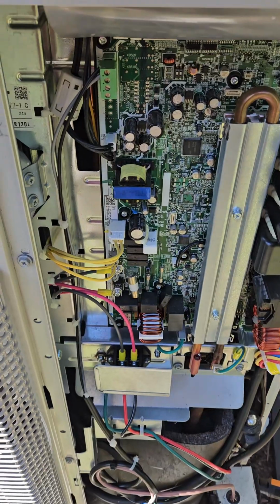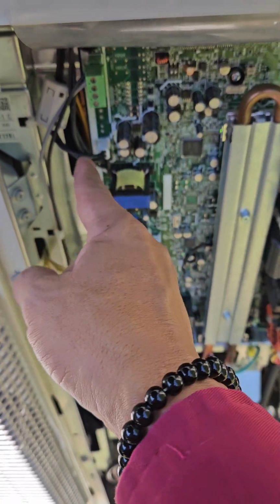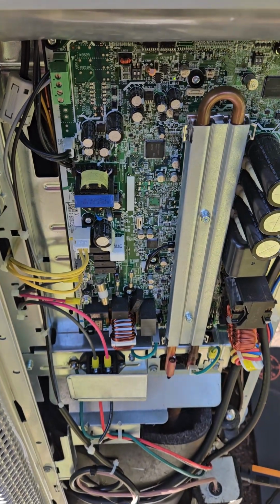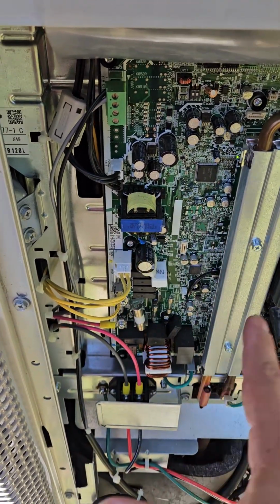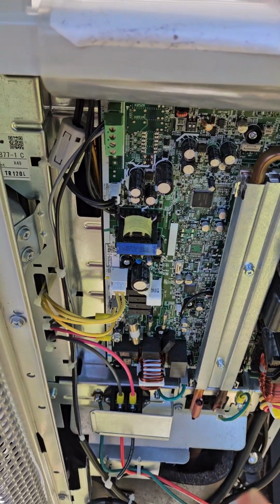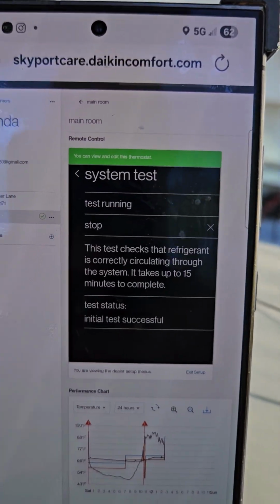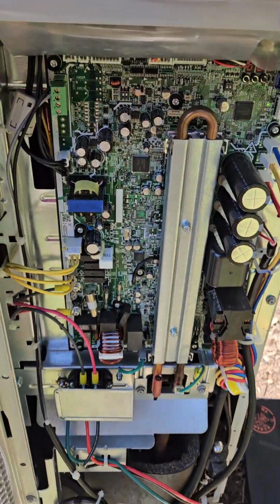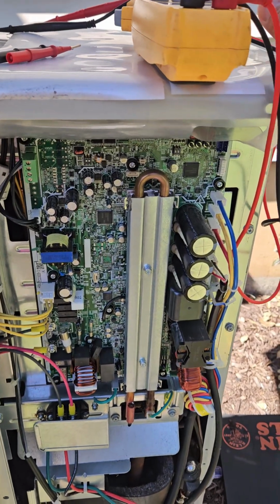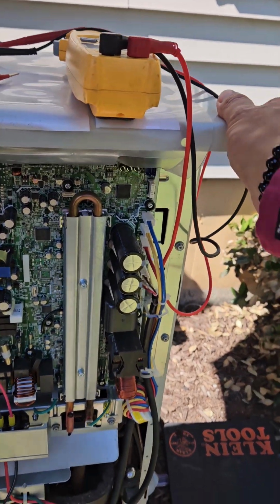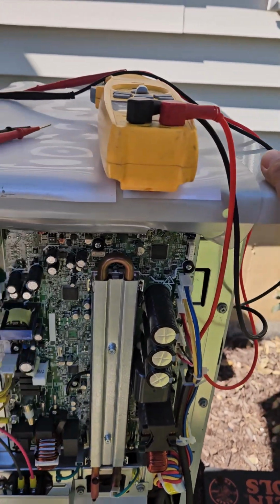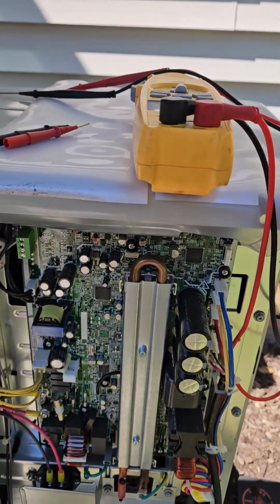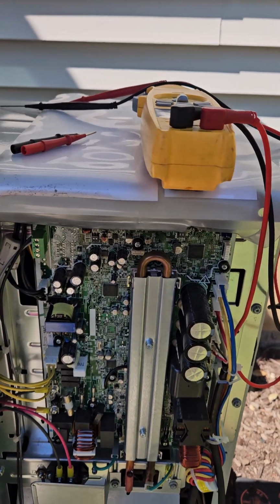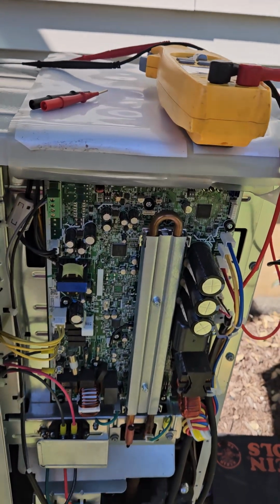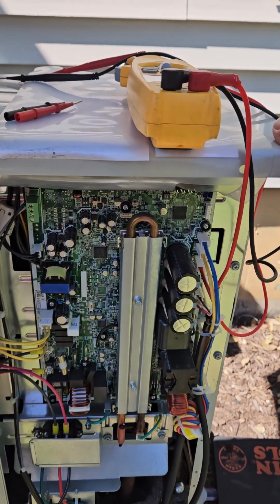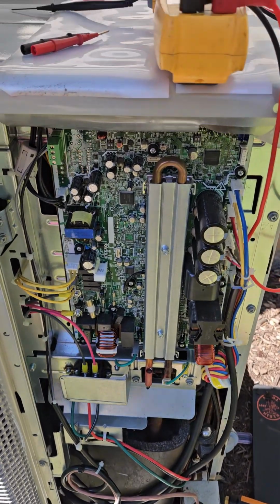Alright. Okay, so the pressure, resistance, and the actual voltage coming out into the actual switch, that's fine. So all the part of the board is sending the right inputs, and the switch is responding to that, so nothing is wrong with this. I just put the thermostat on running test, as you can see right there, so that way I can see if there are any issues with the code 13, because once the system runs in test mode, it'll tell me if there are any subcodes related to the code 13. So it could be 13 or 1 or 2 or 3, and I think it's all 4 as well. It depends on those codes. After the test, I can see exactly what's going on. So once I receive that subcode, if it is 1, I'll let you guys know what that code means and what we need to do in order to fix that problem.